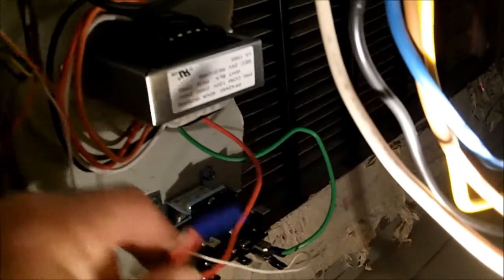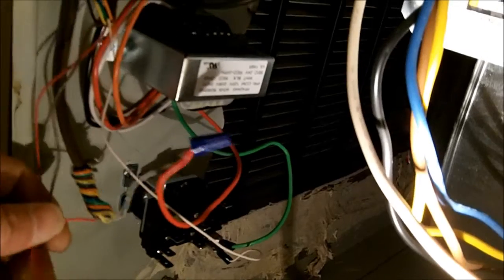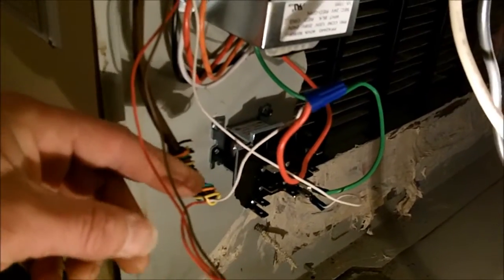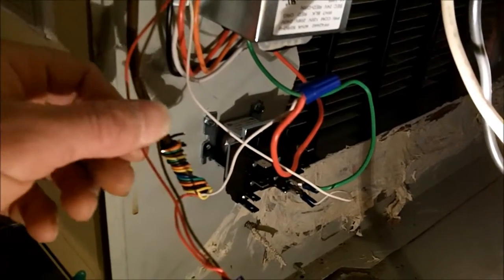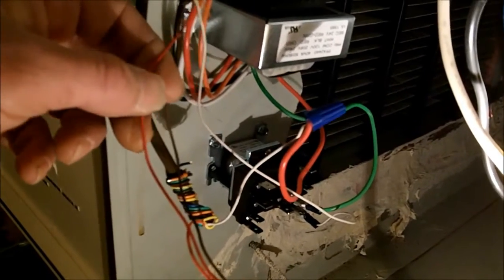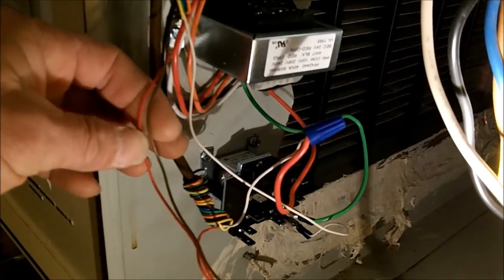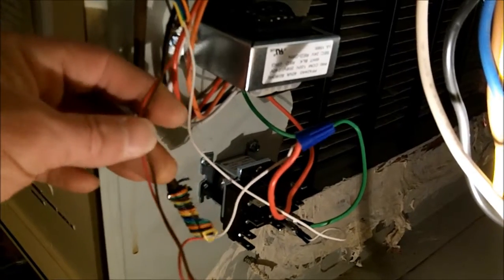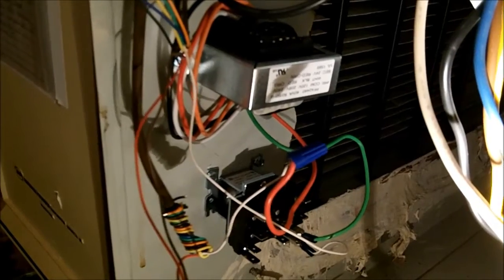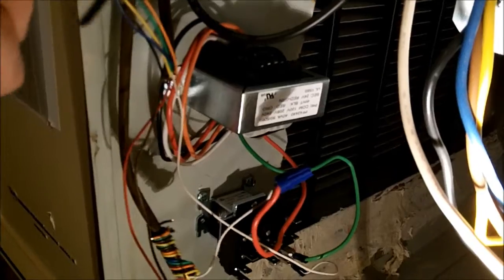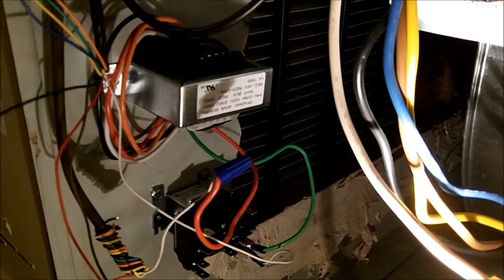Then what I've done is I took my hot from the transformer and I ran it up through this wire right here, fed it across, hit the float switch, it came back, ran it back across, and here's the red wire. I'm using 8 wire because I found a bunch on the job just laying there. And what I'm doing is coming out from the red, from the opposite side of the float switch, and I'm going to feed my 24 volt hot to the humidistat, and the brown is going to my H terminal on the humidistat. So that's going to feed the relay on the humidistat, and it'll send power back to green, I believe. I have to check. No, black is what I'm coming back with. So anyway, that's the beginning of it, and we'll go through each step as I go through it.